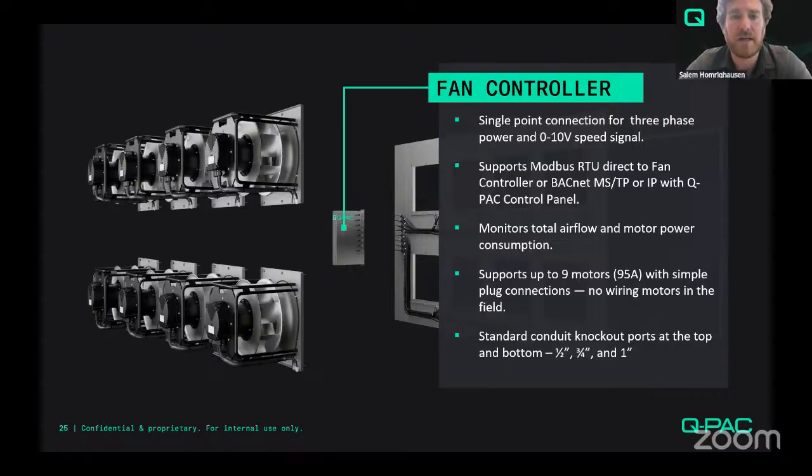That's just kind of one way. The other features of the fan controller are it's got overcurrent protection for each individual phase of each individual ECM plug fan. There's also the controls, a pretty sophisticated control board inside of that as well. Q-PAC has its own team of electronics and firmware engineers that build that. So the plan is that it's really going to unlock the future of the product. There's some other R&D pieces in there too that we're pretty excited about.